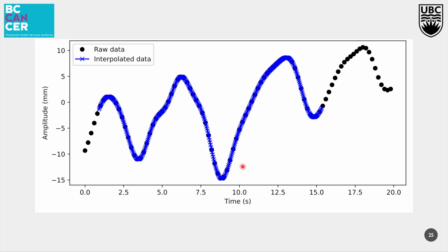And then one of the major problems with the software, I suppose, that runs the respiratory phantom was that it performed an automatic truncation in order to match the initial and final boundary conditions of the trace such that it could be looped. And as you can see here with the raw data, clearly these initial and final points would not be able to be cleanly looped.